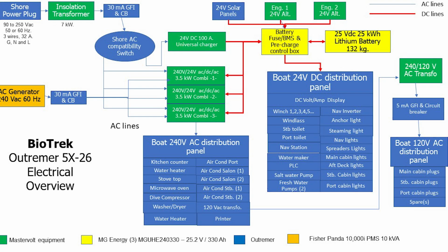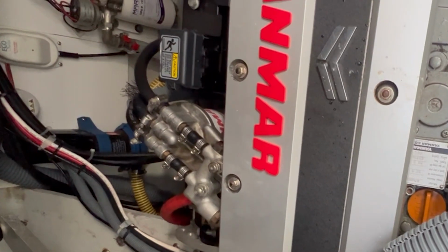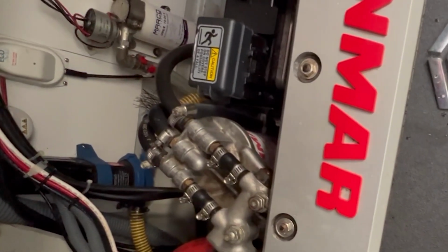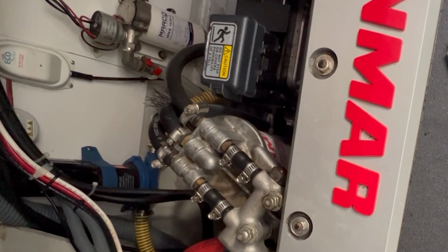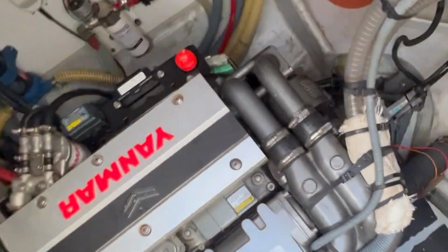In the original installation, the 24-volt alternators went directly to the DC distribution panel. The old alternators were 60 amps running at 24 volts. The new alternators are 185 amps at 28 volts, which means they need a regulator so we don't overcharge.